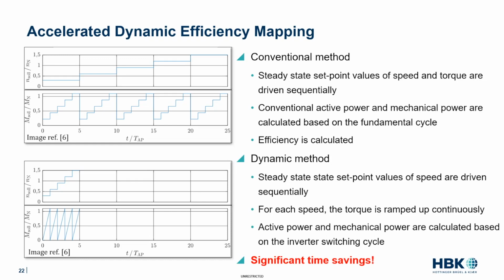After the data acquisition has started, one has to measure for a certain number of fundamental periods. Then the measurement is stopped and the inverter may drive to the next steady state operating point. During this measurement, all relevant parameters such as the RMS values, or for efficiency mapping the active power quantities, are calculated. This takes a lot of time, because you have to drive from one steady state operating point to the next and always wait until steady state conditions are really reached. This is only to show the procedure; in reality, you have quite a lot of different torque and speed combinations. For high speed values, perhaps not all torque values may be driven because the maximum power is limited, but the procedure is like this and it takes quite a lot of time.